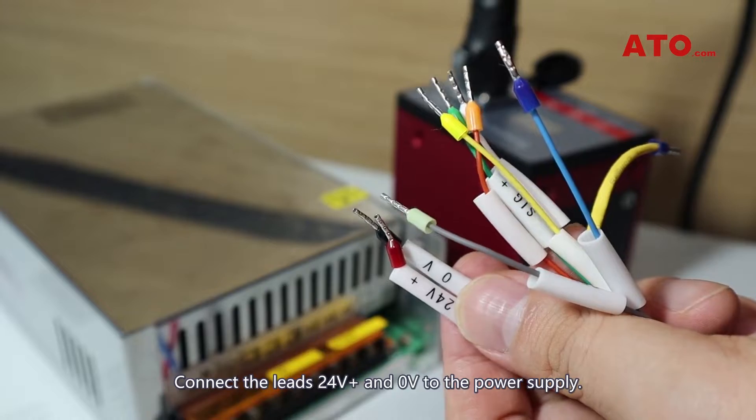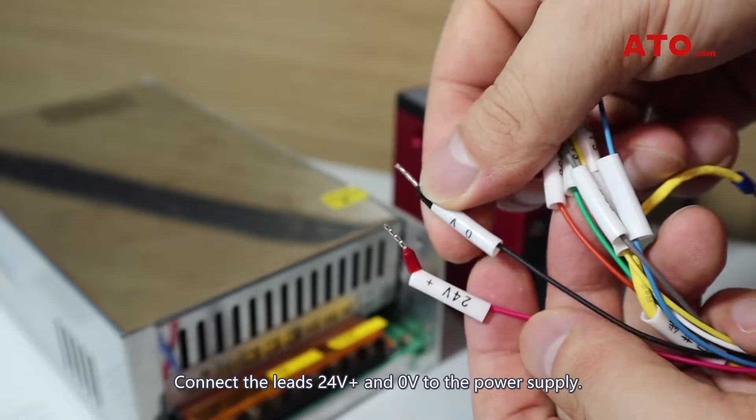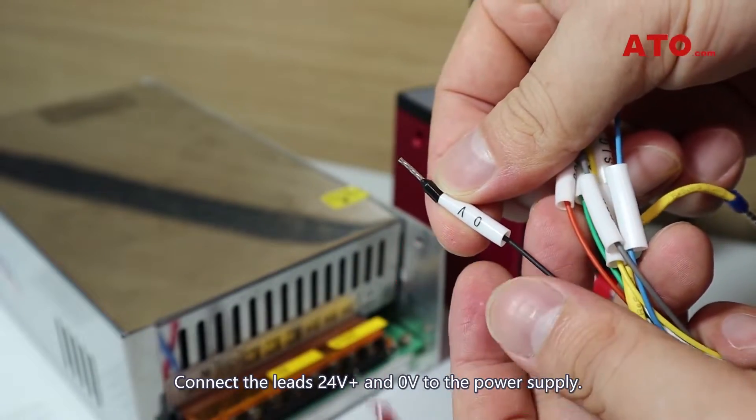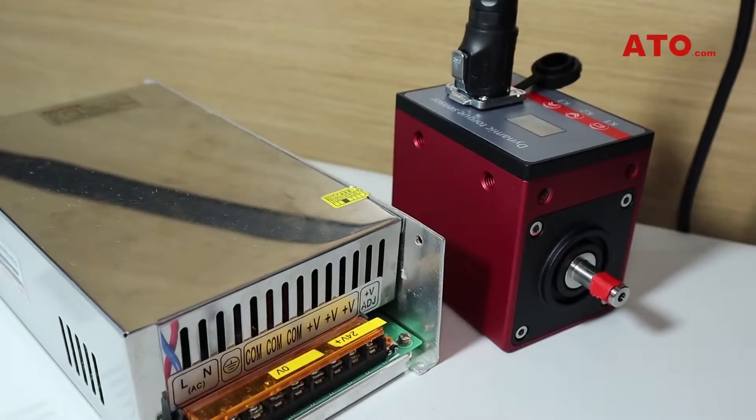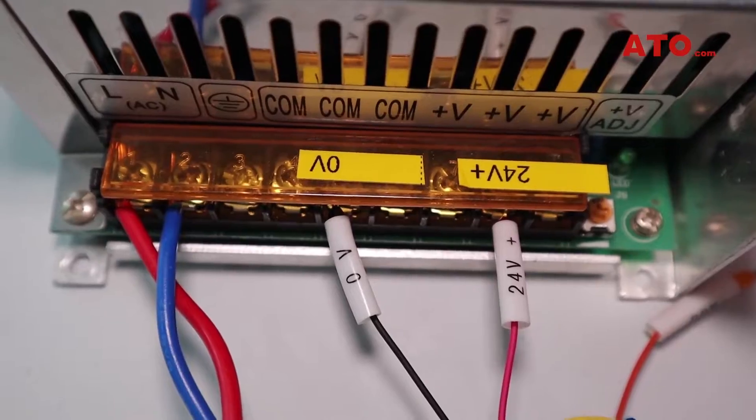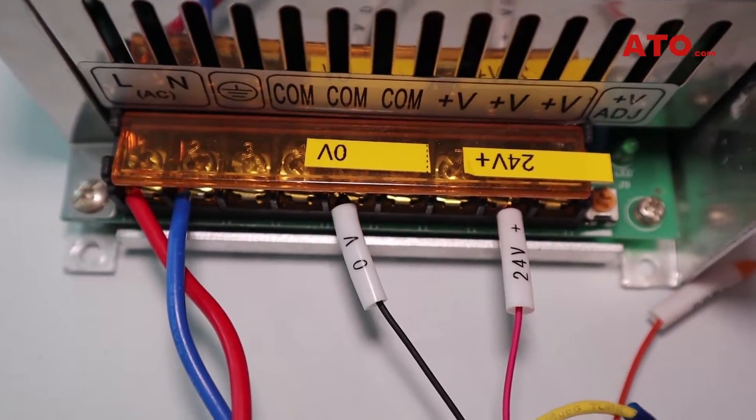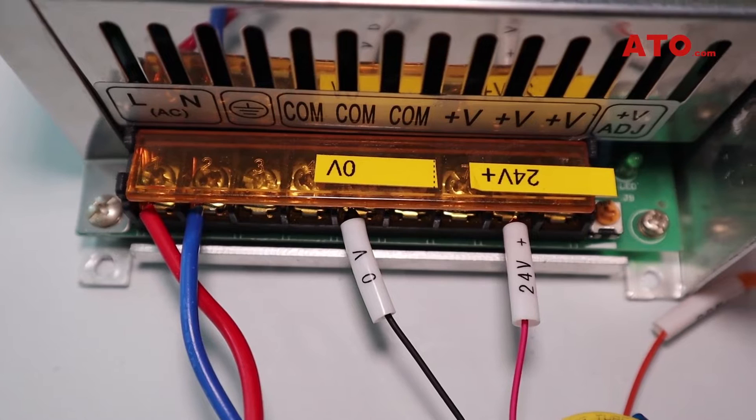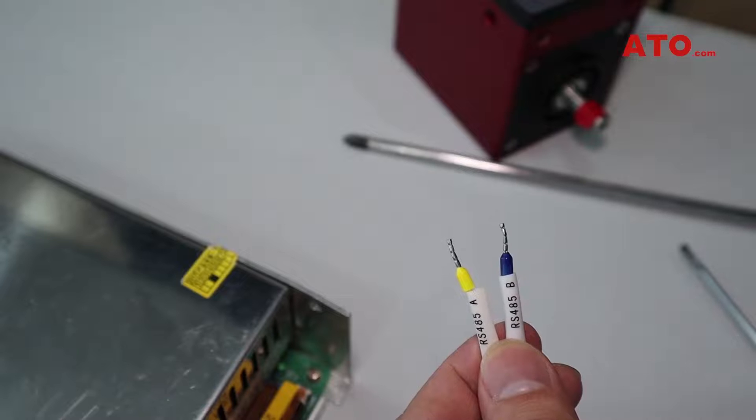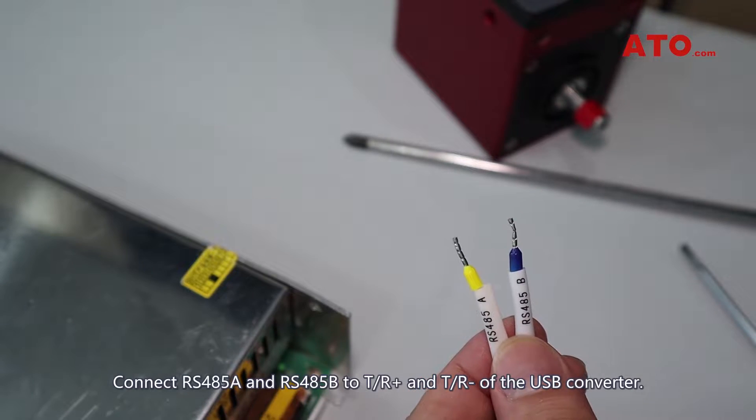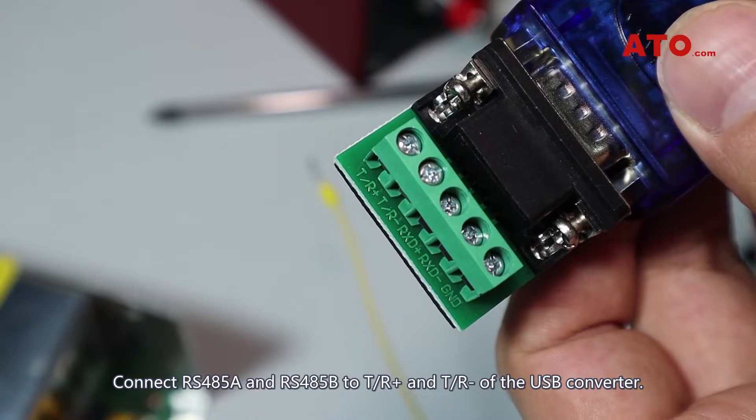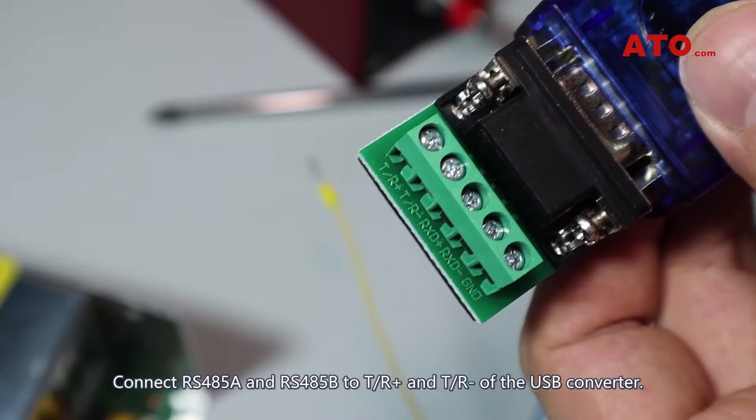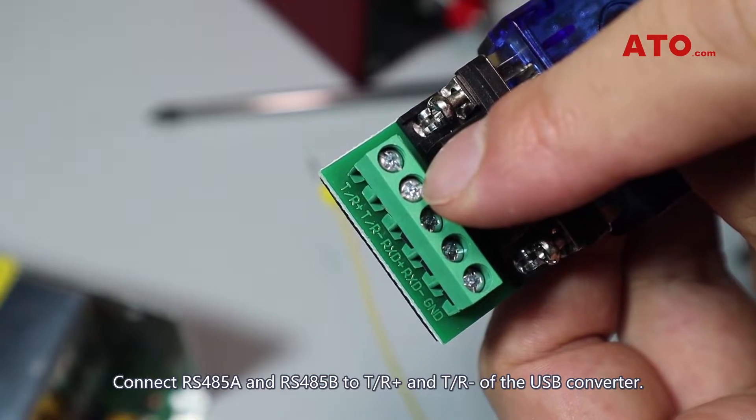Connect the leads 24V+ and 0V to the power supply. Connect RS485A and RS485B to TR-plus and TR-minus of the USB converter.